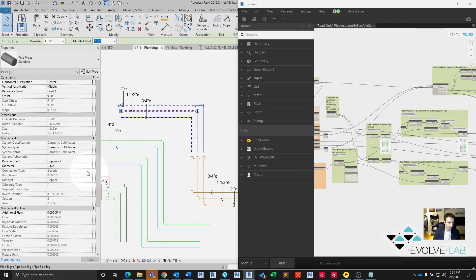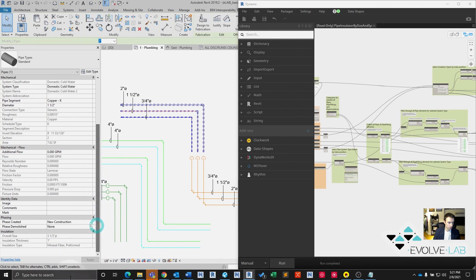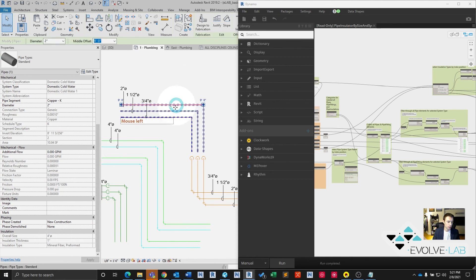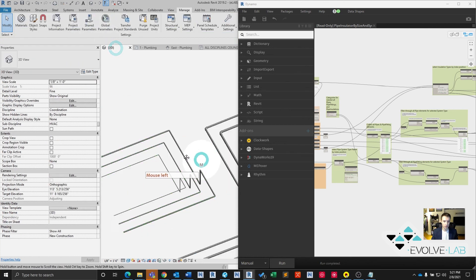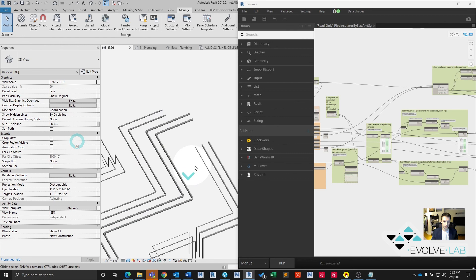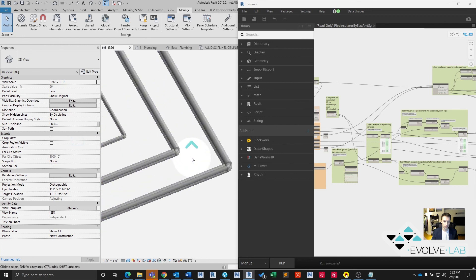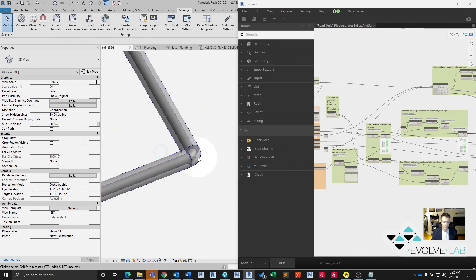And that's exactly what we wanted to see. This insulation is one inch thick. Excellent. That's what we wanted. This insulation is half inch, what we wanted. And one inch, what we wanted. All right, excellent. That looks like it's working great. We go to our 3D view. Notice that even the fittings got insulated.